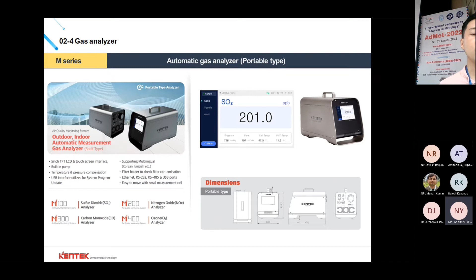And this is brand new for the gas analyzers. The screen is bigger than before, from 5 inch to 7 inch, and the software is upgraded so that the user can operate it more easily than before. And this is the calibration system. The calibration system is made up of a multi-gas calibrator, zero air generator, and the ozone standard reference photometer. The calibration system is for calibrating gas analyzers such as SO2, NOx, and CO. And the ozone standard reference photometer can be used for calibration of the O3 generator in a multi-gas calibrator and the O3 analyzer and generator as well.